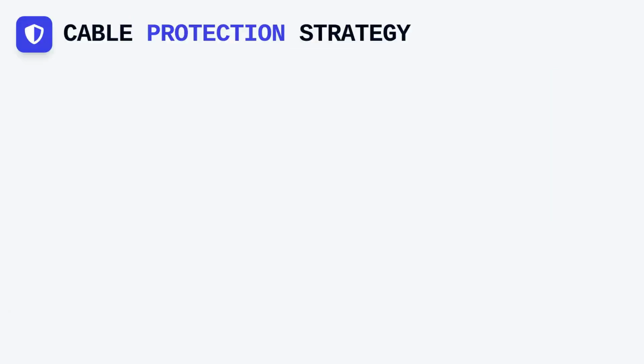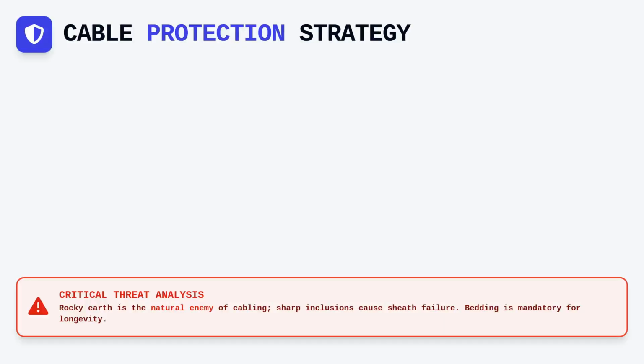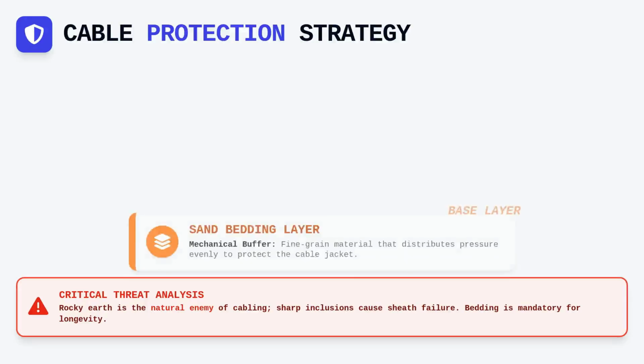Once the trench is excavated, the interaction between the soil composition and the cable jacket becomes a primary concern. Raw, rocky earth is the natural enemy of high-performance fiber or copper, as sharp inclusions can easily lacerate or puncture the outer sheath. To mitigate this risk, we employ a sand bedding layer, which provides a neutral, compliant interface between the harsh native soil and the cable itself. This fine-grained material acts as a mechanical buffer, distributing localized point pressures evenly across the surface of the jacket rather than concentrating them on a single protrusion.